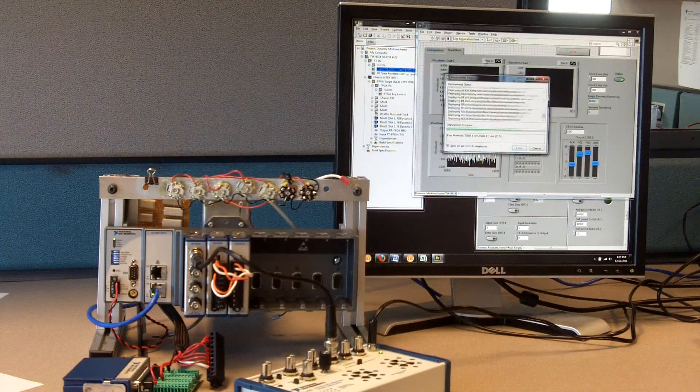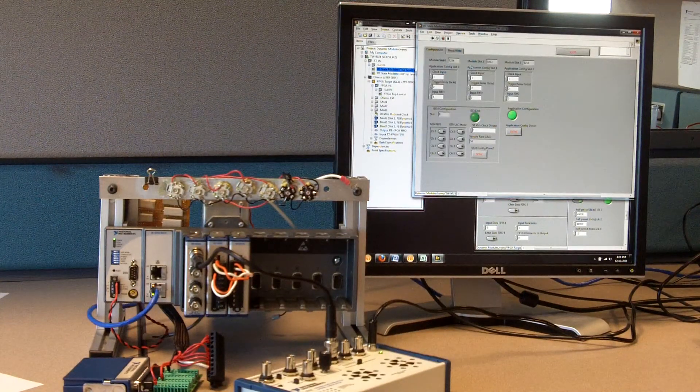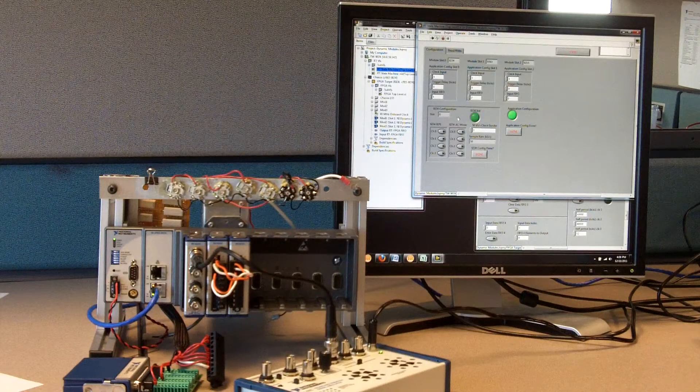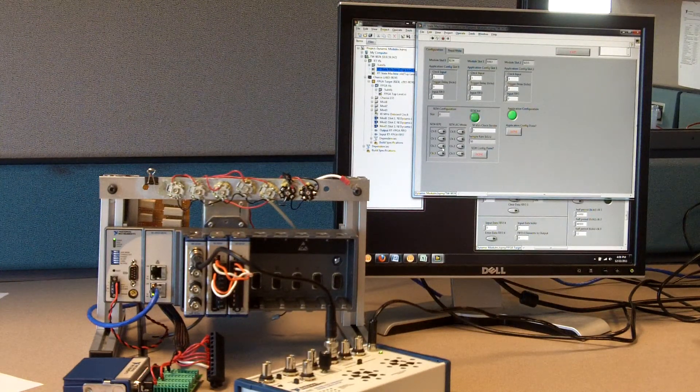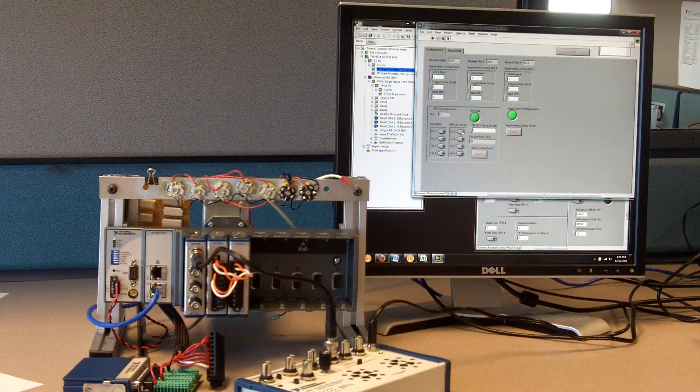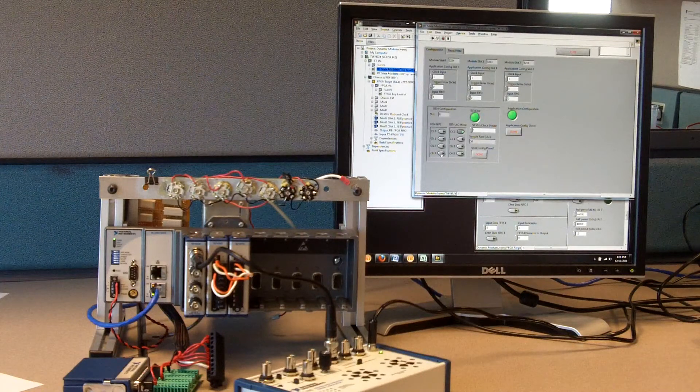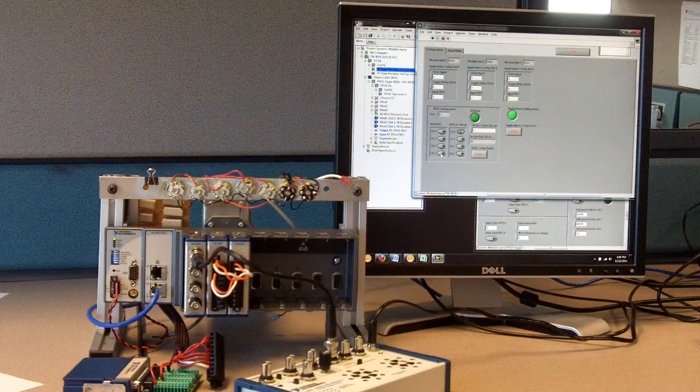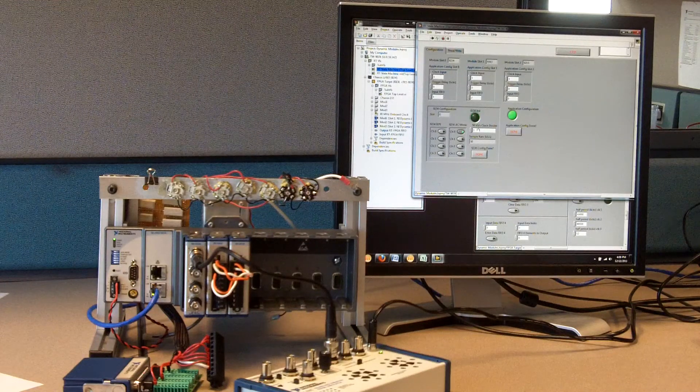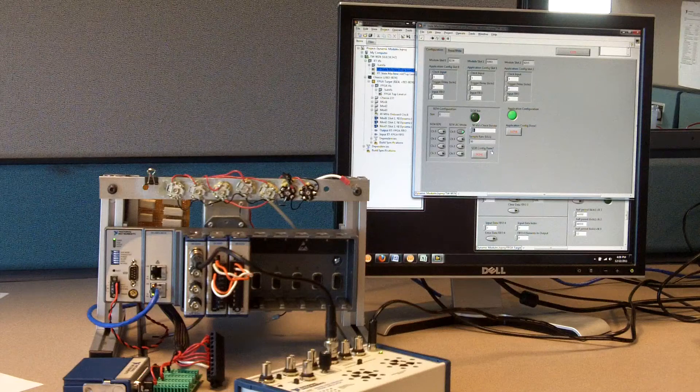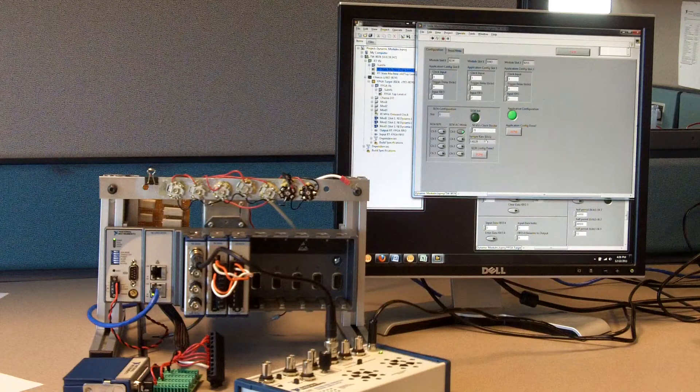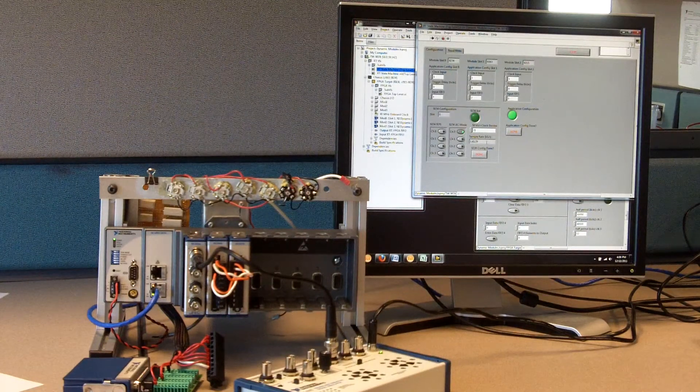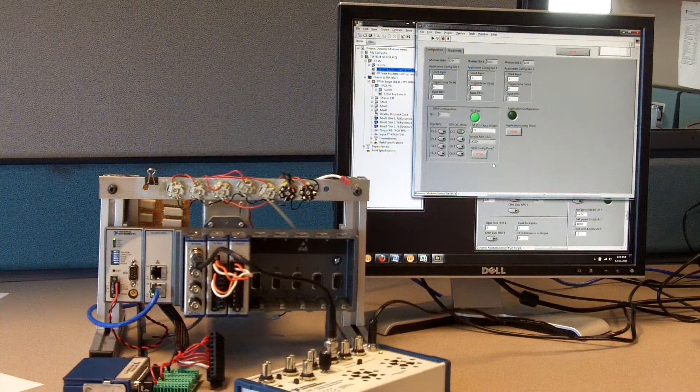I'm going to run this again. So it'll go back through and again ask the FPGA which modules are in which slots. You can see now it's telling me the 9234 is in this first slot. And because the 9234 is a more sophisticated module, it has some additional configuration. So I've built this pane to let me enter some of that data, turning on and off the AC coupling. I can also go through and enable IEPE excitation. And because this is a self-timed module, it has an onboard clock which is going to control the ADC. I can choose what sample rate I want. I'm going to set this to a 1.6 kilo sample rate.